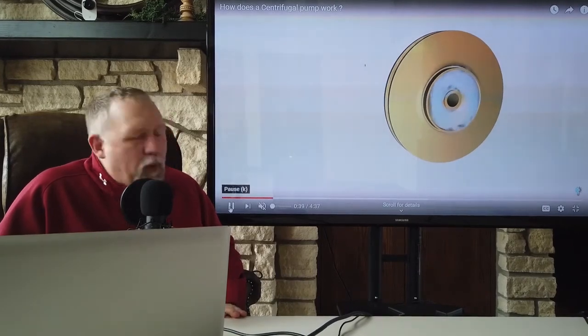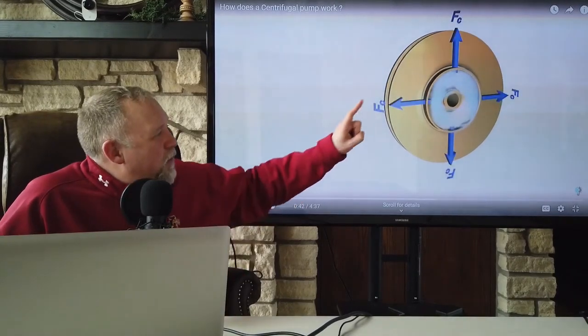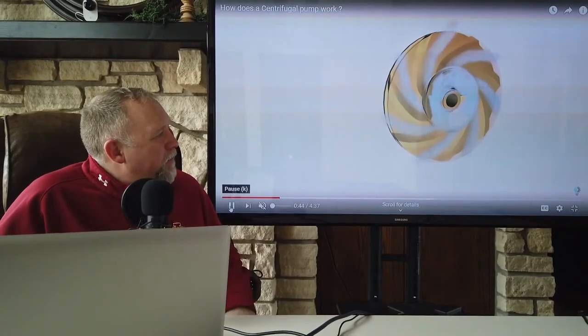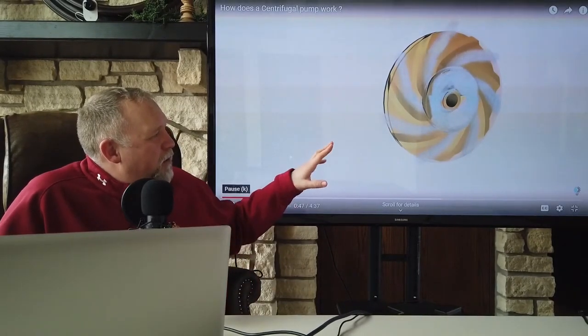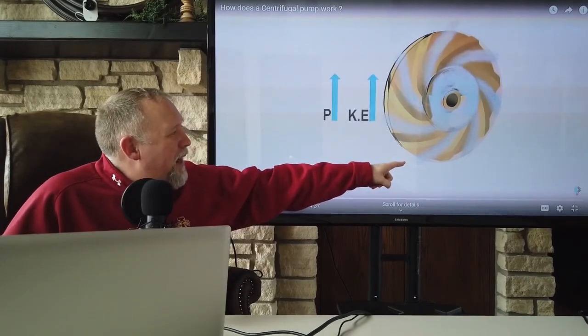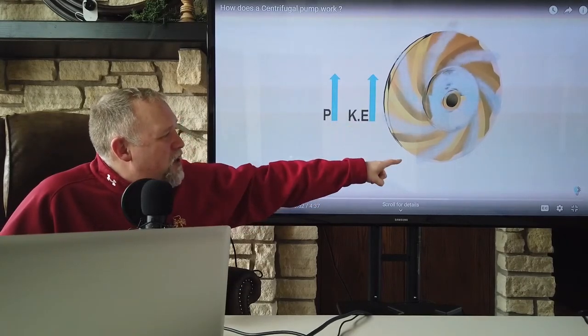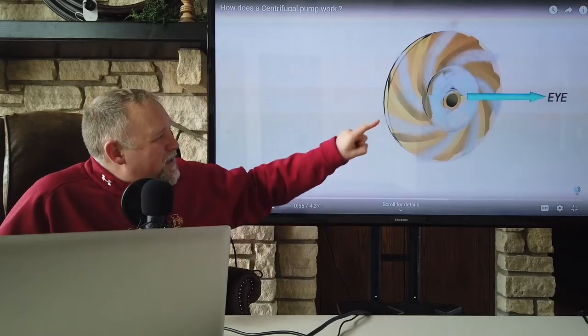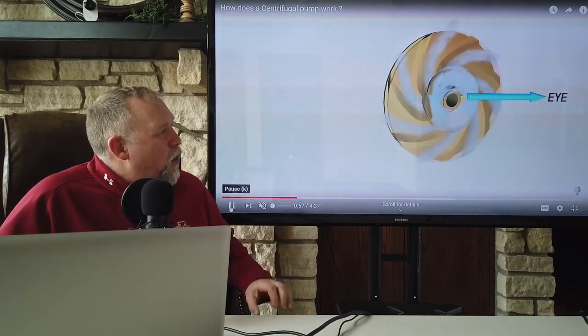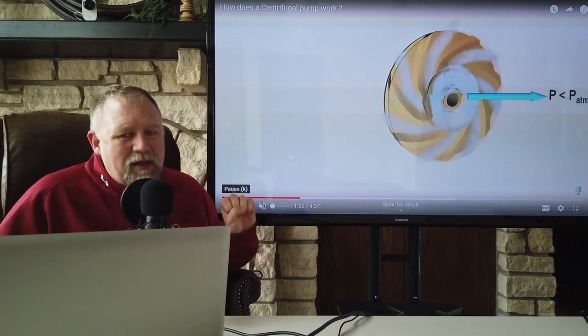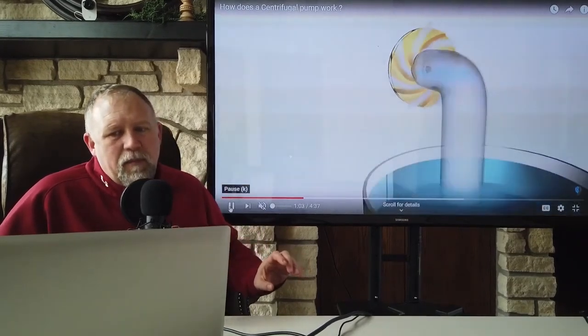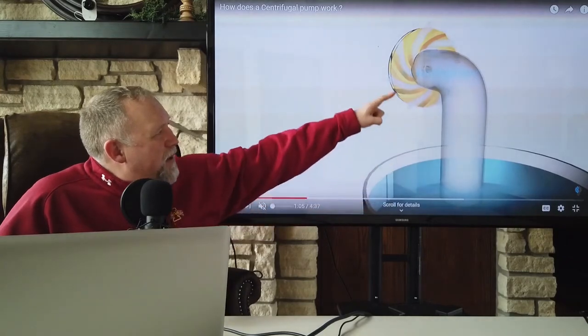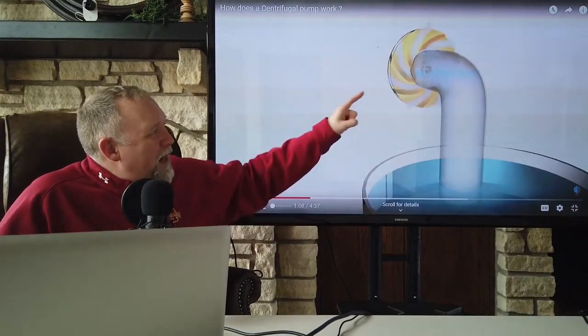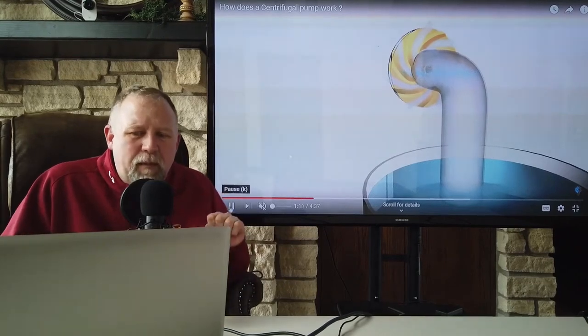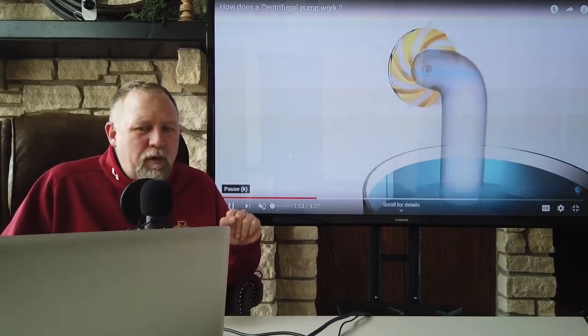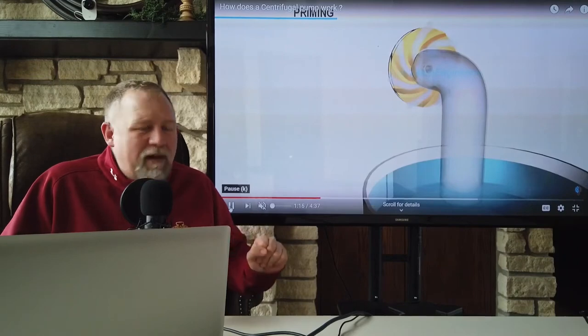and the lowest point of pressure is going to be there in the center, right? It's going to spin, push water out in all directions. Out here at the outlet, that's where pressure and kinetic energy is at its greatest. But at the center, the eye of the impeller, where the water is getting sucked into, that's going to be at the lowest pressure, right? This is a pipe that goes to that suction. Right there has to have a certain minimum pressure to avoid that term called cavitation.